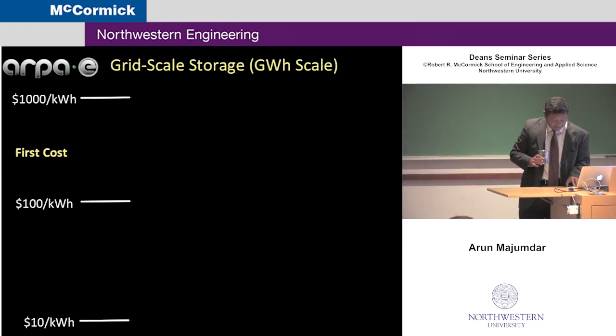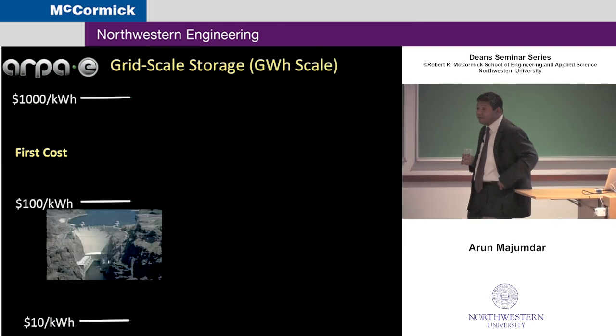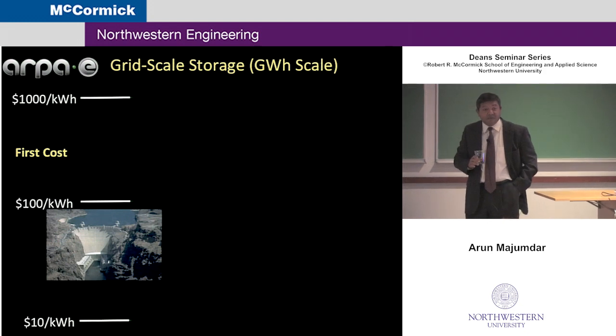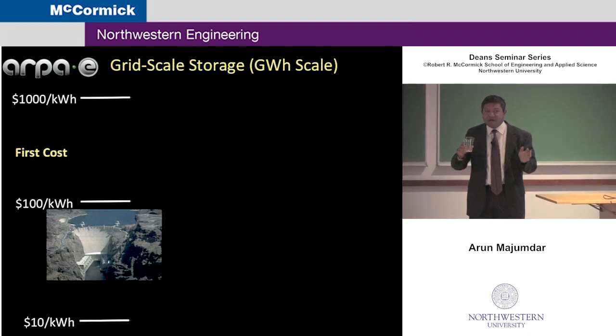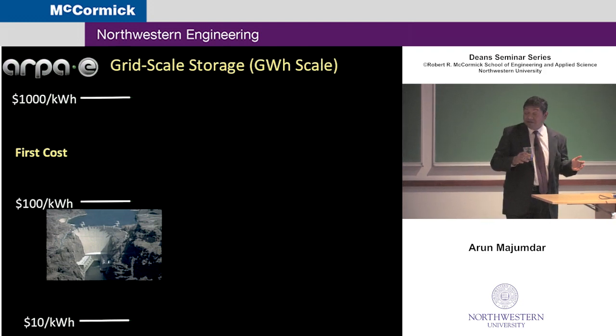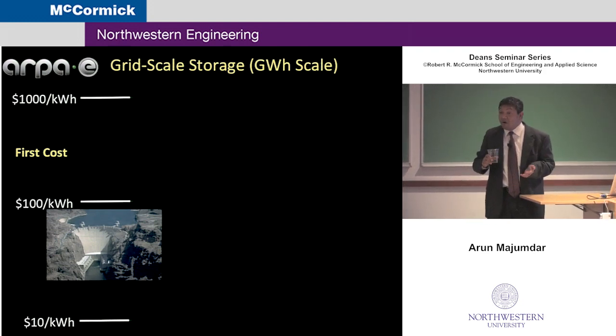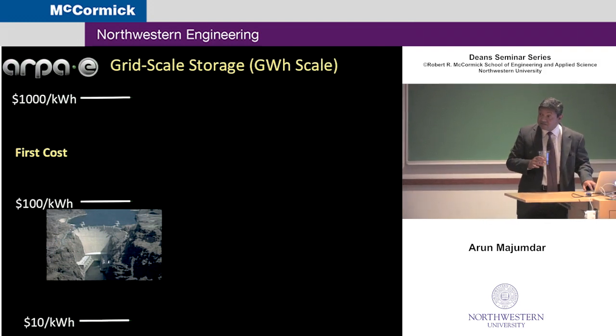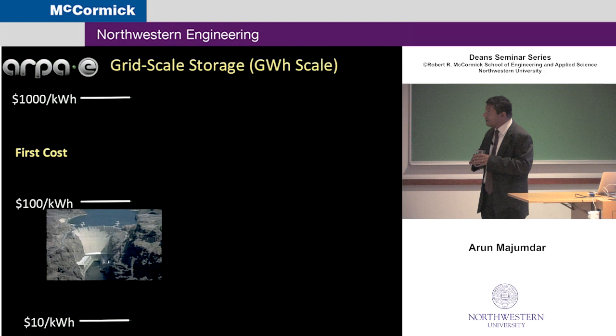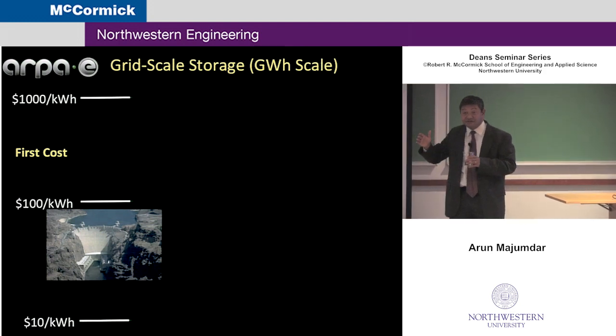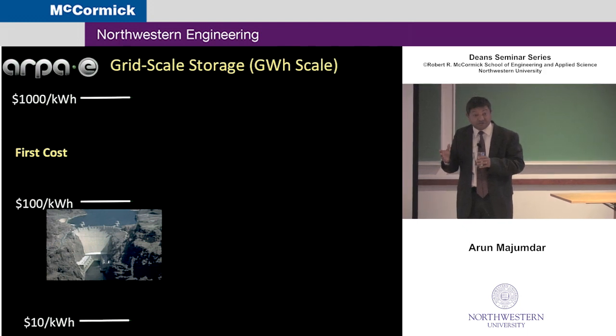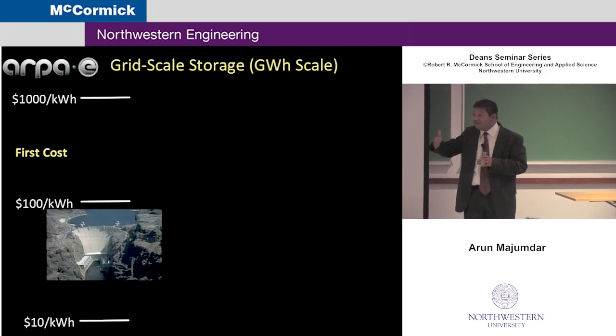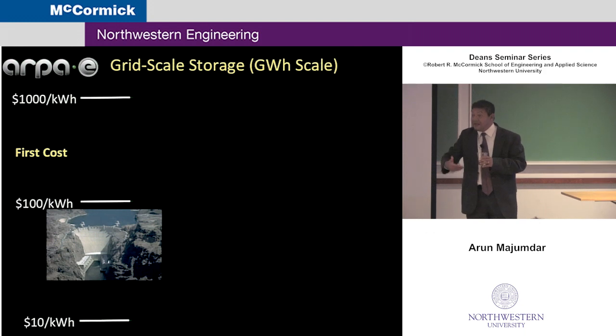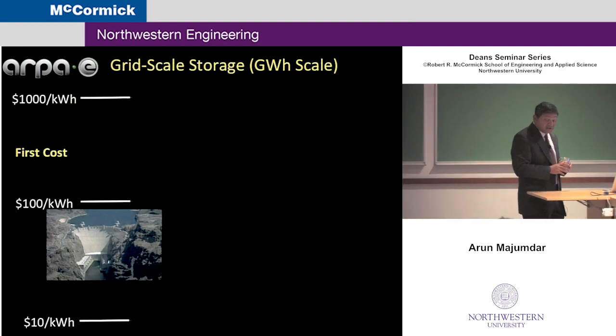Why $100 a kilowatt hour? Because the existing technology, pumped hydro, is at about $100 a kilowatt hour, whereas all the battery technologies, flow batteries, etc., used to be about $1,000 a kilowatt hour, or about $500 to $700 a kilowatt hour. So we created a program in grid scale storage saying you've got to get to $100 a kilowatt hour capital expenditure, have round trip efficiencies of about 80%, and last about 5,000 cycles, because then it really matters. That would be a winning technology.